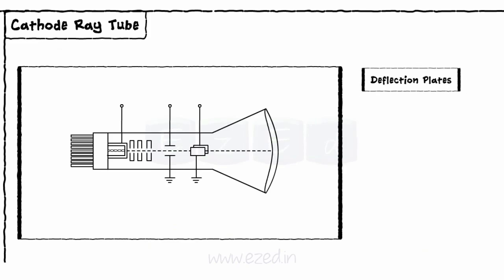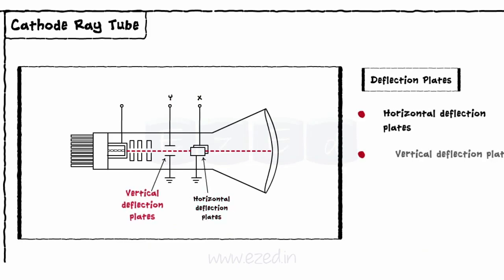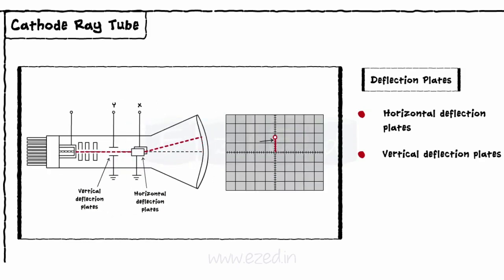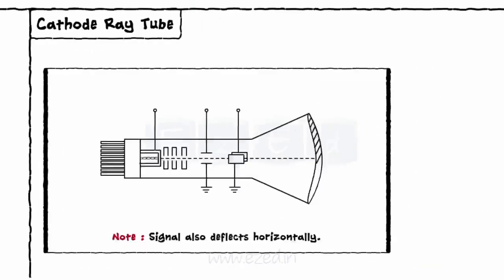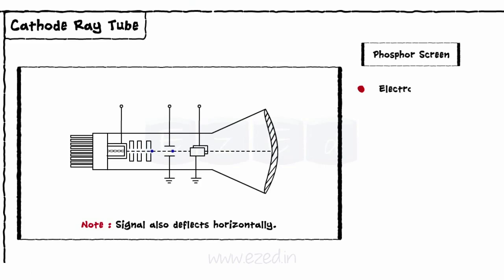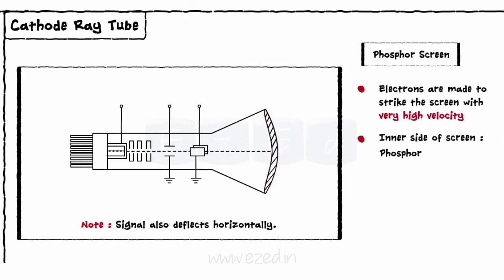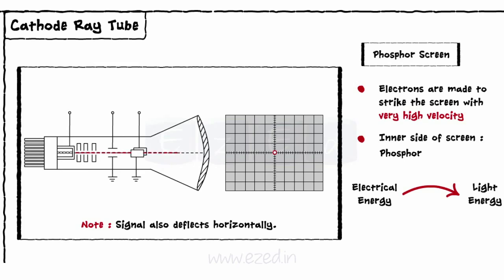The next section is deflection plates. A focused beam with a very high velocity is then passed through X and Y deflection plates. These are horizontal deflection plates and vertical deflection plates respectively. The forces on both plates are controlled such that the waveform will be displayed on the screen. The last section is the phosphor screen. The focused, accelerated, and deflected beam is then made to strike the inside part of the CRO screen with a very high velocity. The inner side of the screen is coated with a special type of phosphor. This layer converts the electrical energy into light energy. Thus, whenever an electron strikes the screen with a very high velocity, it generates a bright spot on the screen and the beam moves so fast that it appears as a waveform.